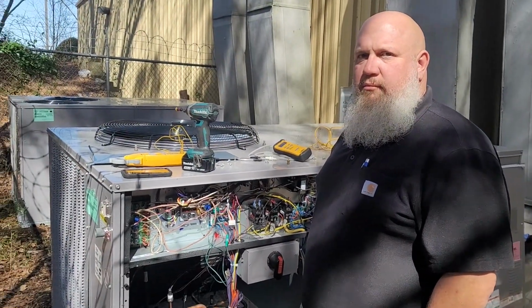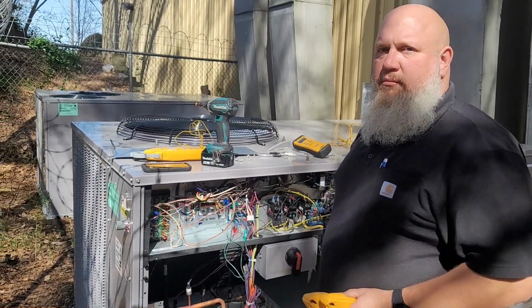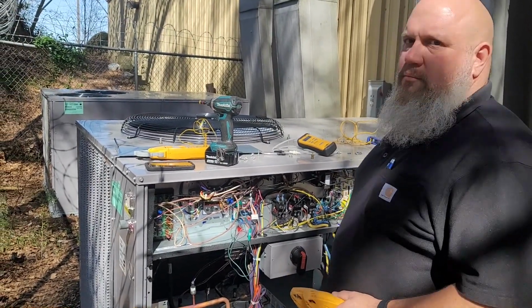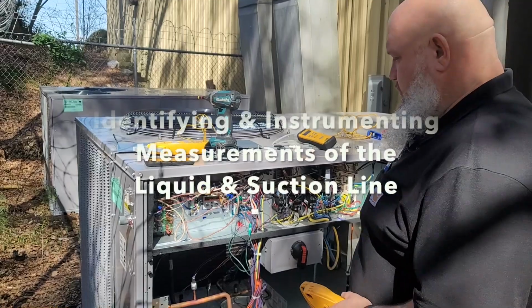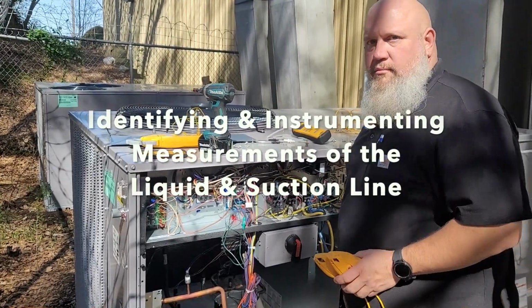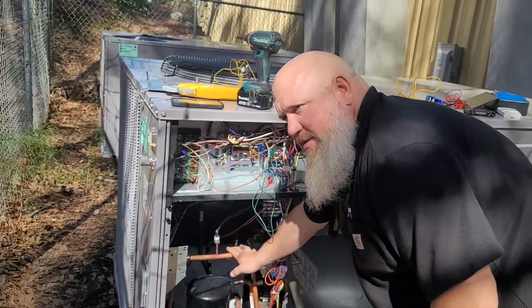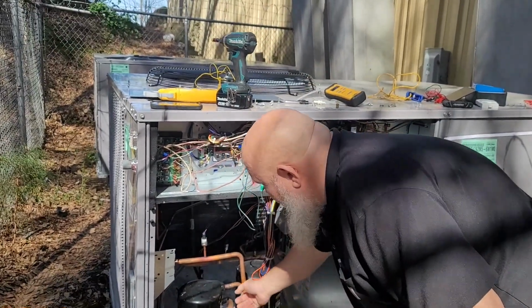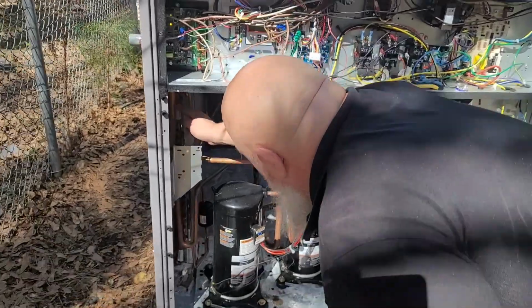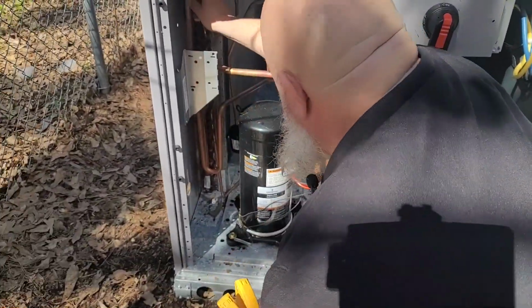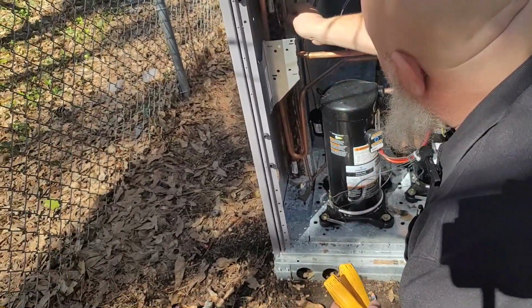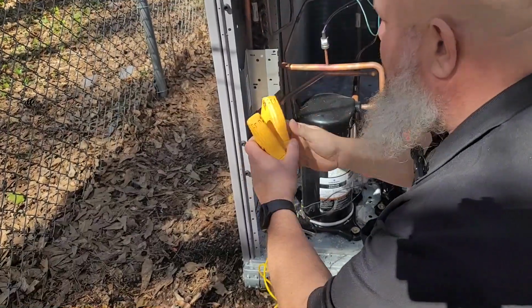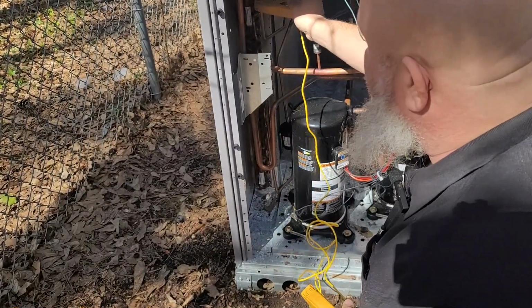Excellent, thanks. Obviously, it's really important to circuit the system. So tell us how you determine what liquid line and what suction line go for each individual circuit compressor. All right. For example, here's your hot gas discharge coming off the compressor. You follow it up to that section of the coil, and then we determine that this one on the top is our hot gas line.